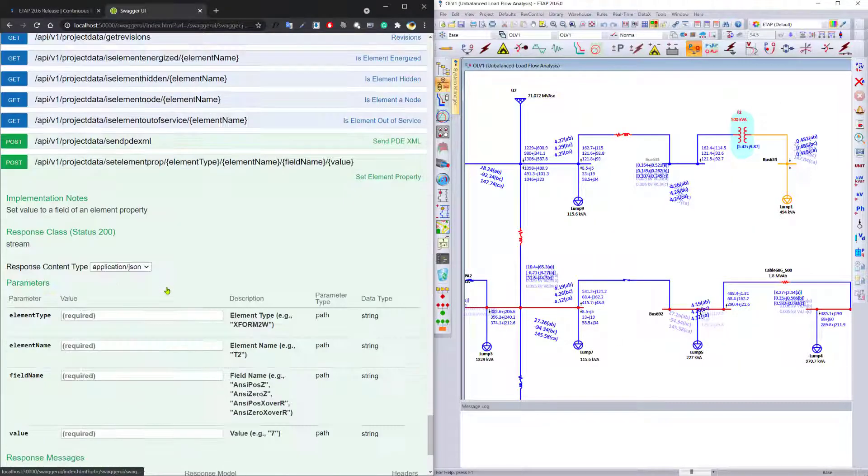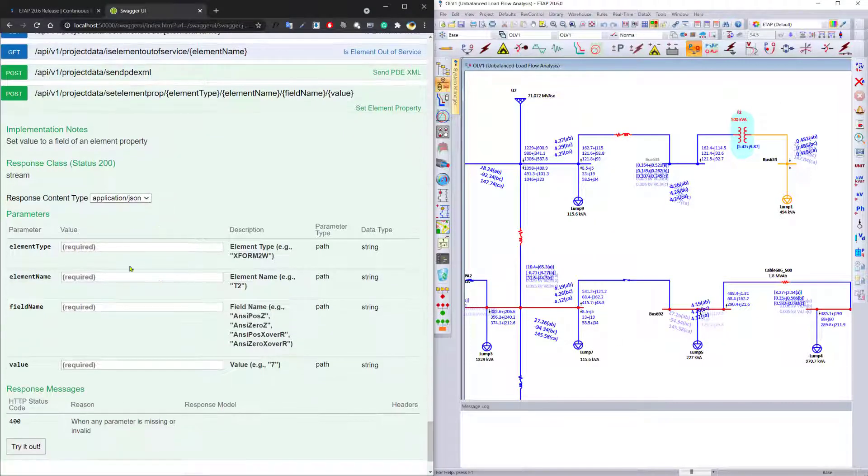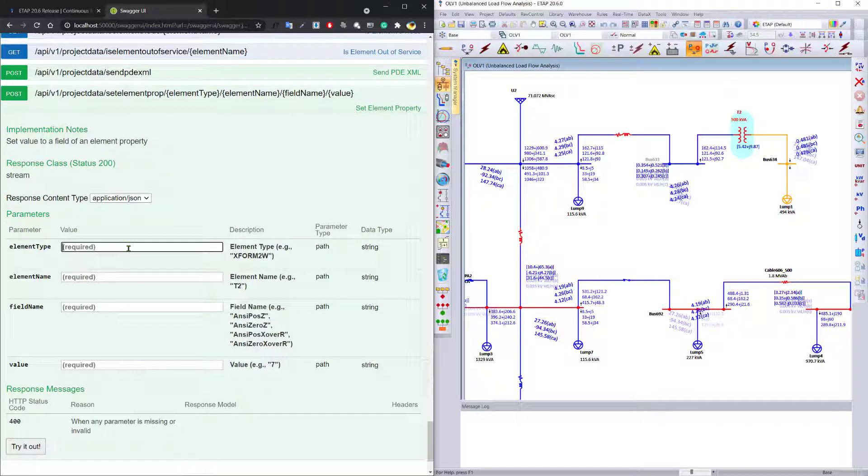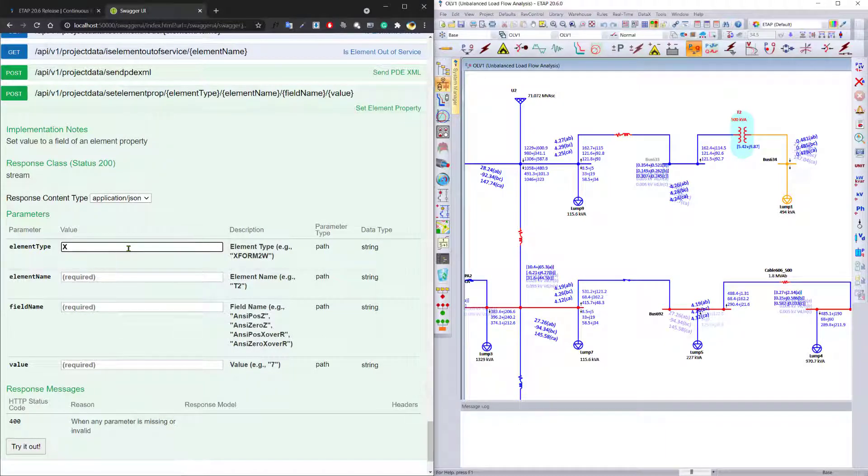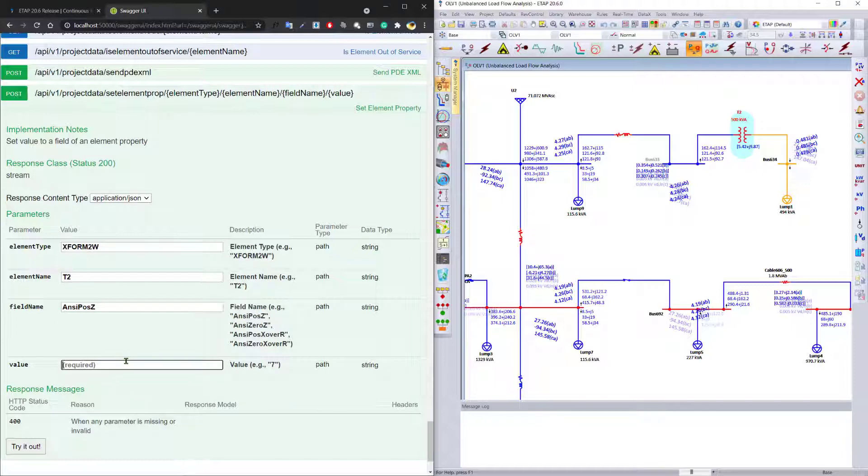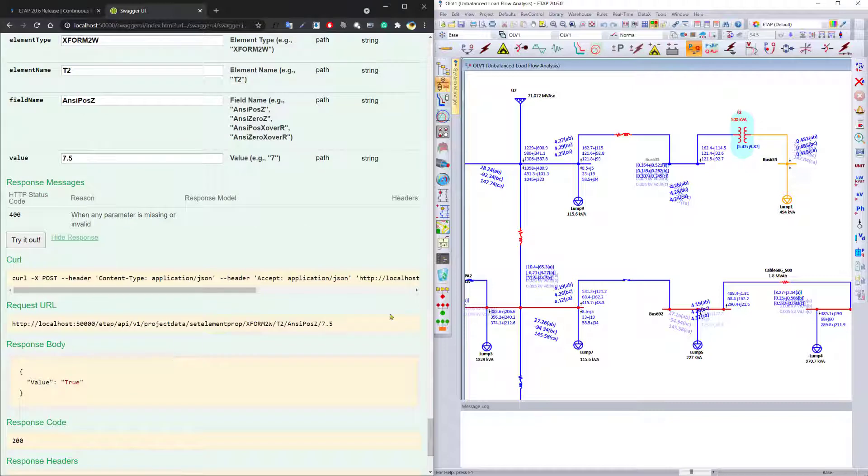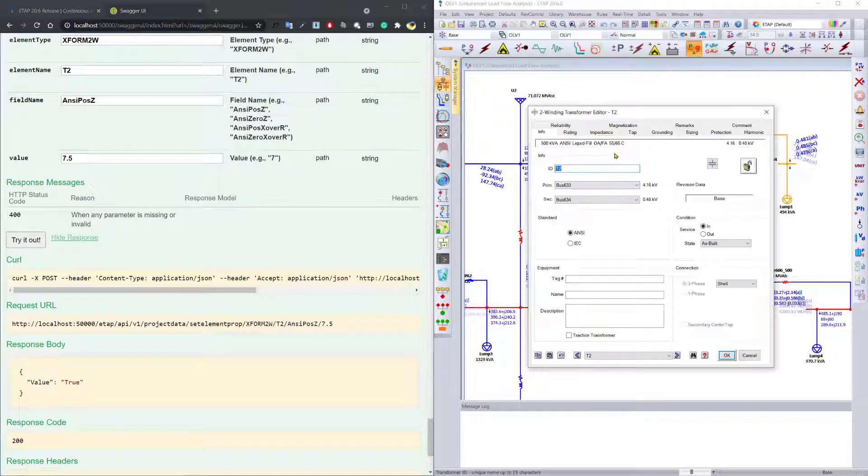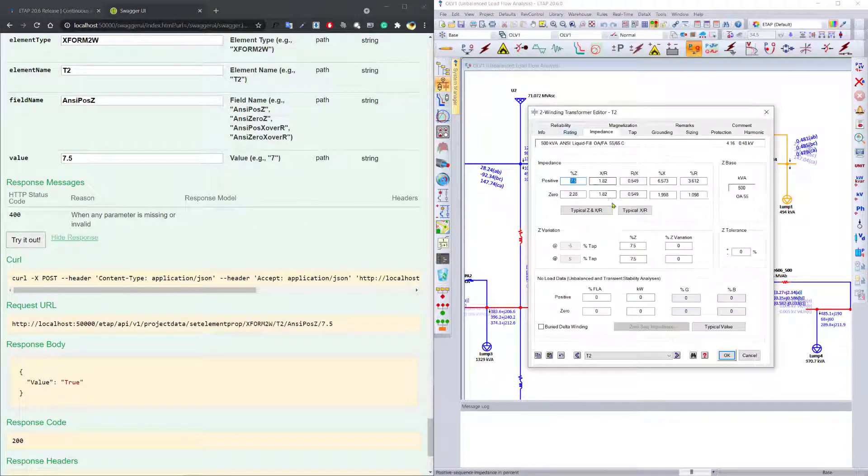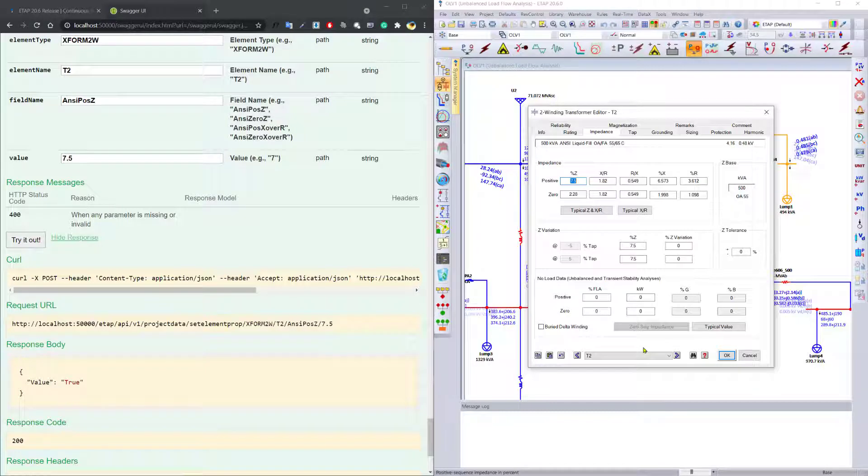You can also use the same tool to set the value of the property for this element. We set the value for the ANSI positive sequence impedance, and the value you would like to set to is 7.5. And we can apply it, and then open up the program to make sure that it actually has been applied.